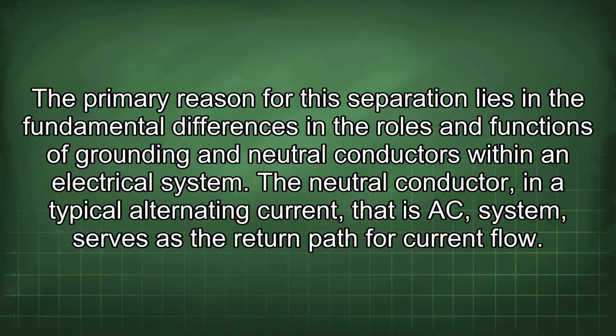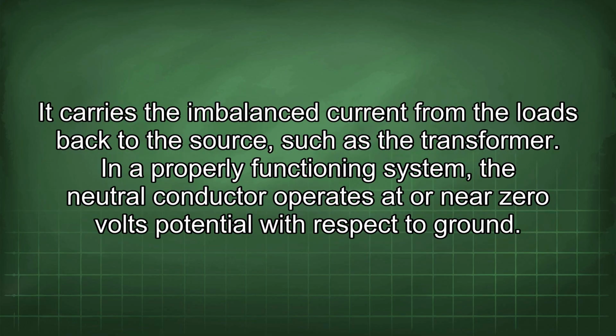The neutral conductor, in a typical alternating current, that is AC, system serves as the return path for current flow. It carries the imbalanced current from the loads back to the source, such as the transformer. In a properly functioning system, the neutral conductor operates at or near 0 volts potential with respect to ground.